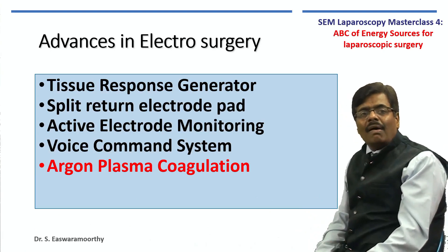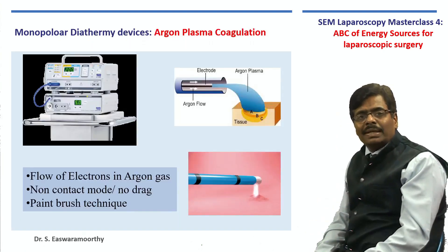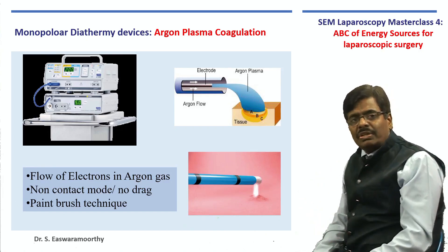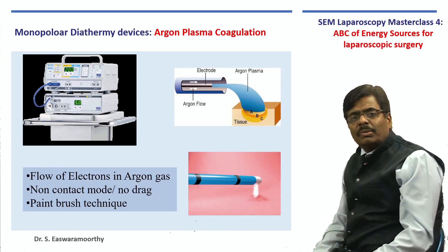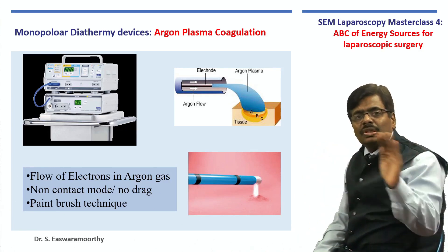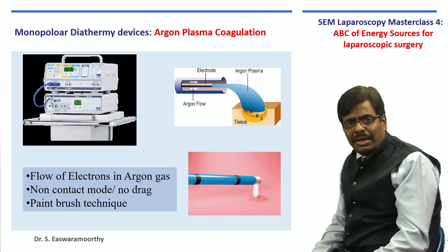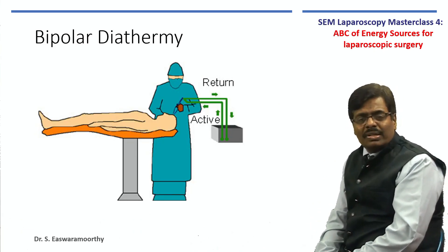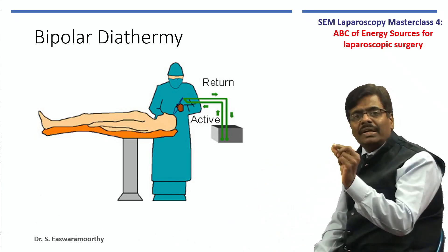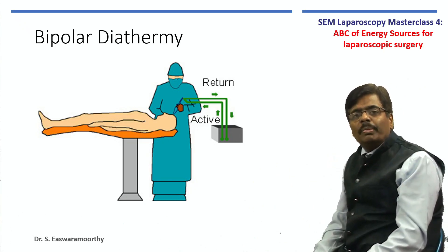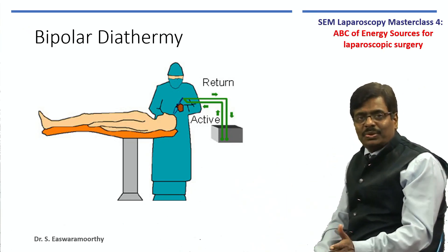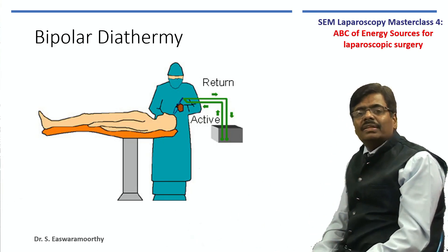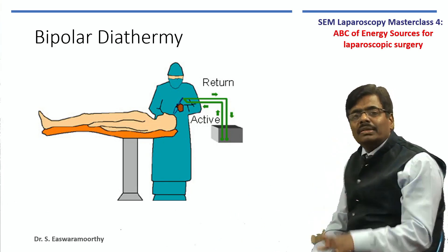The next important electrical device is argon plasma coagulation — not necessarily used in laparoscopy — where thanks to the argon plasma, electrons flow with the least resistance without any drag, like a paintbrush technology. It is mainly used in liver surgery for surface coagulation when there is oozing. Bipolar diathermy is now increasingly used. The advantage of bipolar is that both the active and indifferent electrodes are the two jaws of the instrument, so the patient is not part of the circuit — making it very safe. However, conventional bipolar is not versatile; it cannot do cutting, and instruments tend to stick.